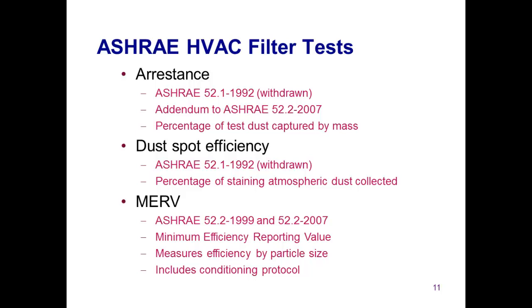An improved test was developed in ASHRAE Standard 52.2, 1999, and revised somewhat in Standard 52.2, 2007. It's the MERV rating, or Minimum Efficiency Reporting Value. In this test protocol, efficiency is measured in 3 different size intervals. This protocol also includes some conditioning of a test filter, or loading of the filter with particles, to see if efficiency changes as the filter collects particles.